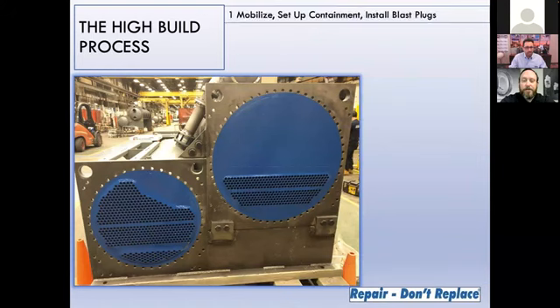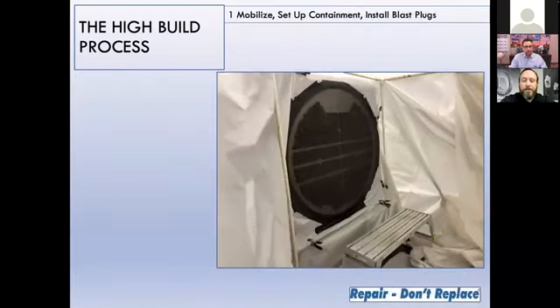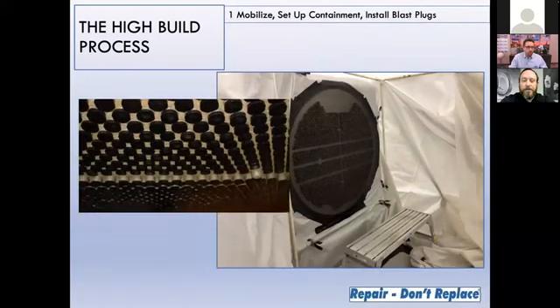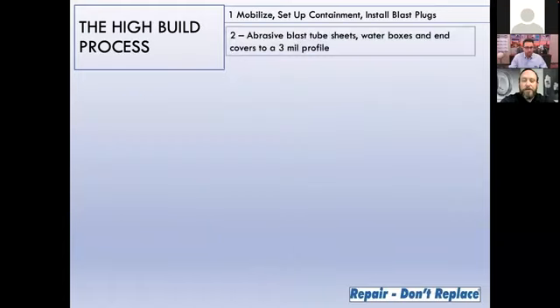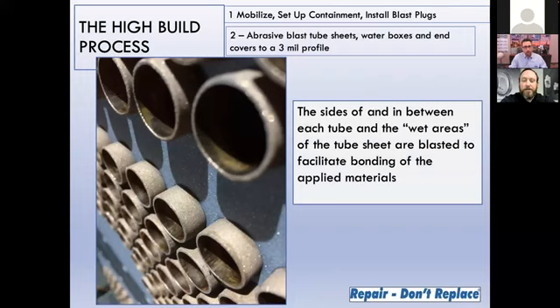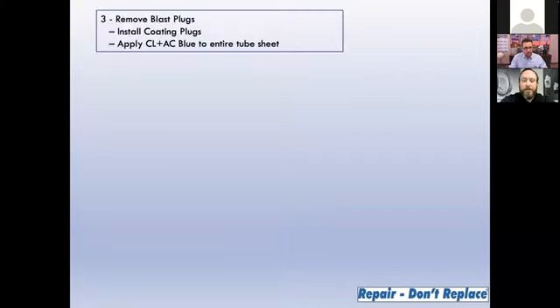ENECON's high build process starts by mobilizing to the job site, setting up containment, and installing blast plugs into the end of each tube. The next part of the process is to abrasive blast the tube sheets, water boxes, and end covers to a white metal or near white metal and a 3 mil anchor profile. We pay special attention to the areas between the tubes, making sure we get the roughness that we need to apply our products. It's the area between the tubes that is the most critical part in preventing any type of galvanic or bimetallic corrosion in the future.